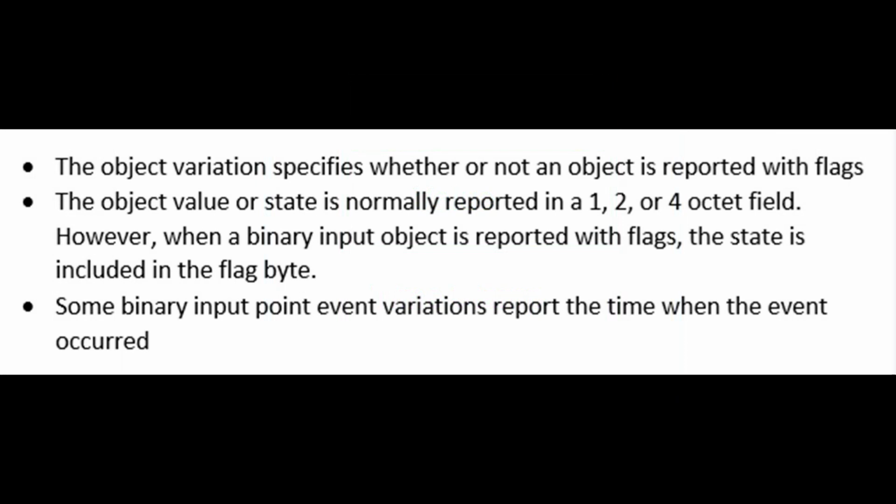The object value or state is normally reported in a 1, 2, or 4 octet field. However, when a binary input object is reported with flags, the state is included in the flag byte. And some binary input point event variations report the time when the event occurred.